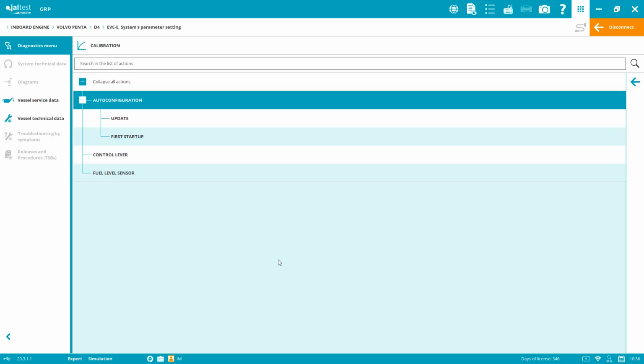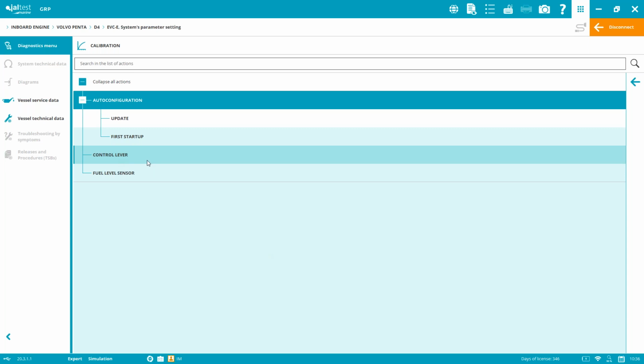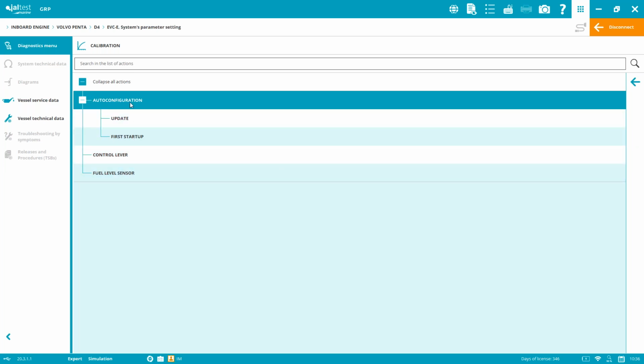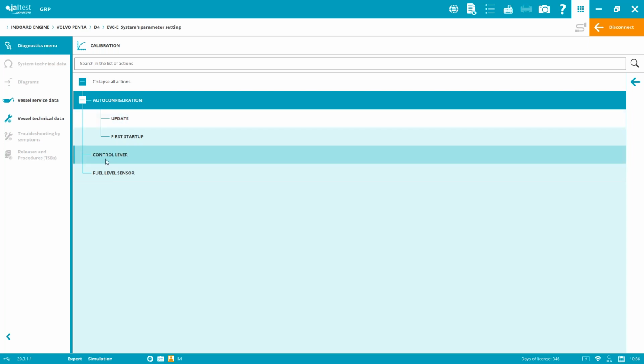Here's something important: if you want to perform, for example, a control lever calibration, if you're changing one lever for another, and it's not the first startup, you need to first click into auto configuration, then click into update, and then click into control lever to do the calibration.